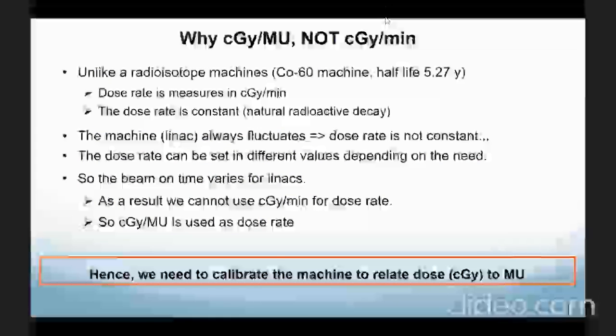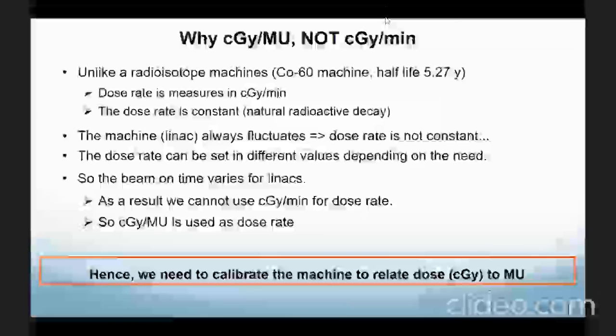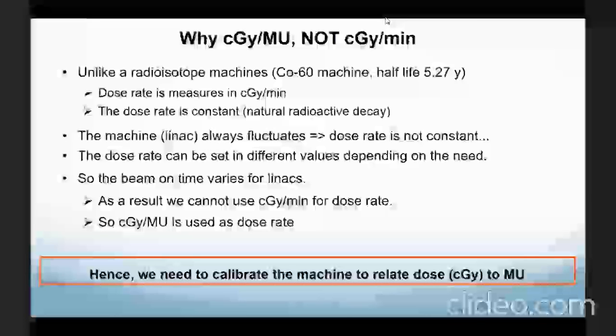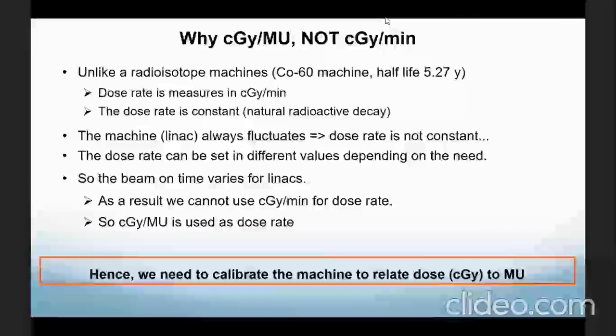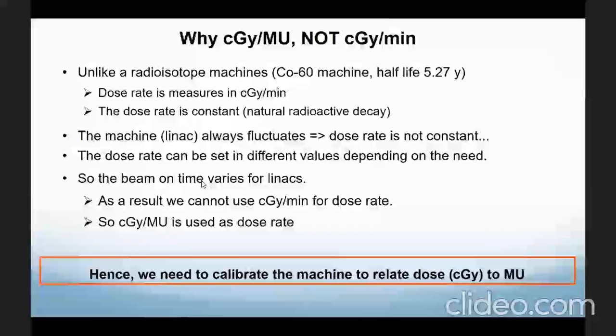As we said, why centiGray per MU and not centiGray per minute? Unlike a radioisotope machine — a radioisotope machine gives radiation based on time — a linear accelerator uses monitor units instead.